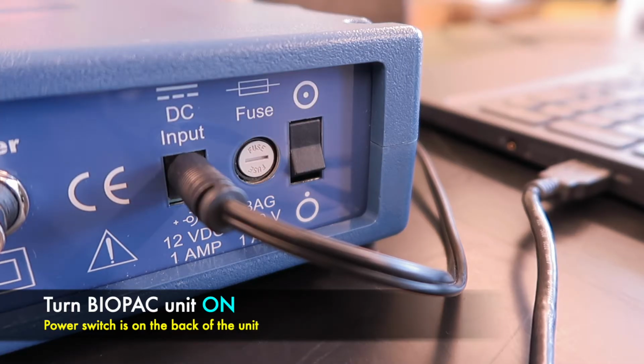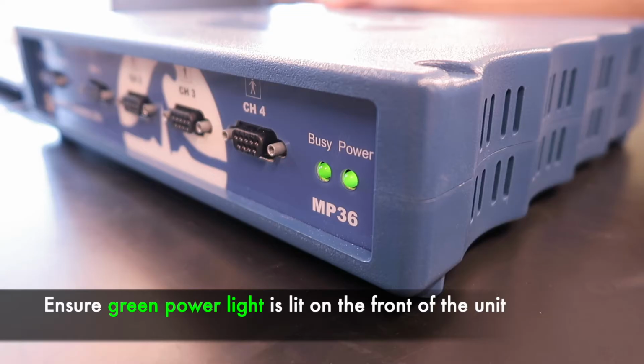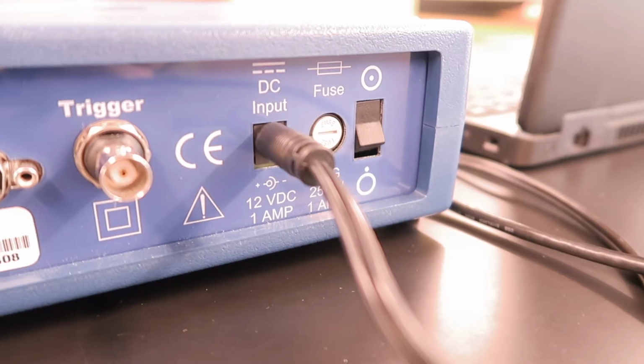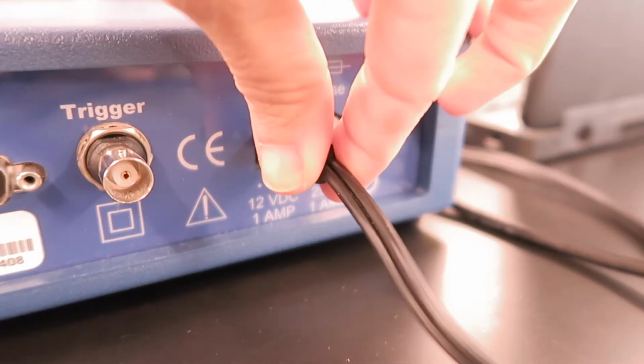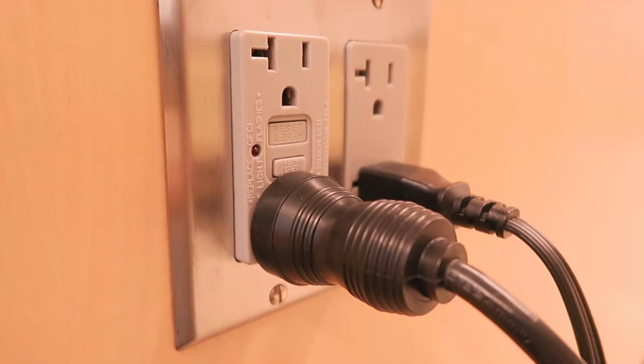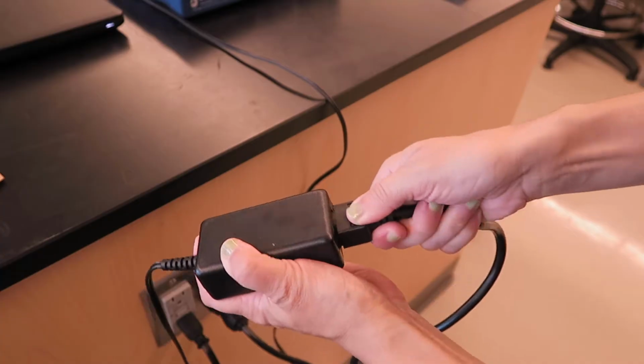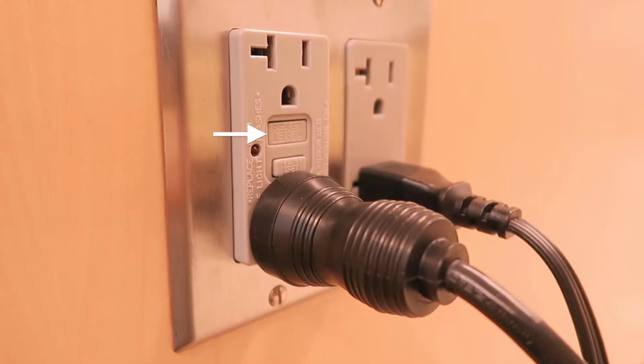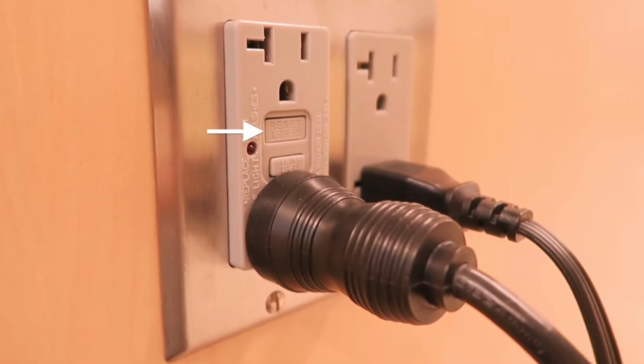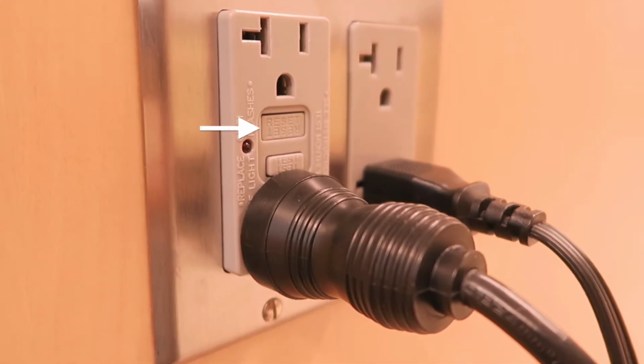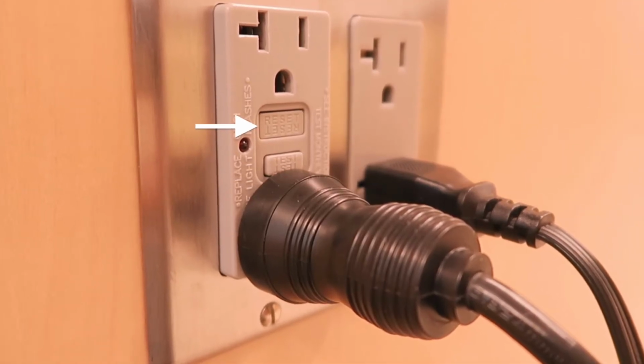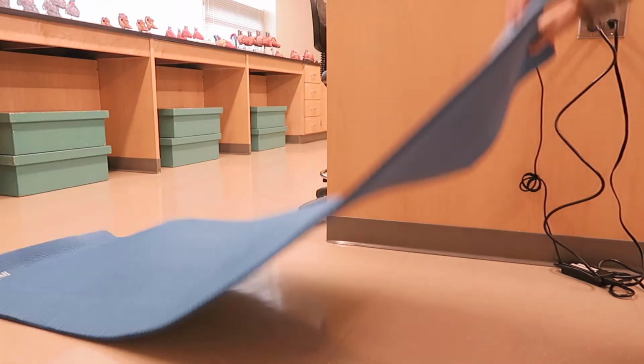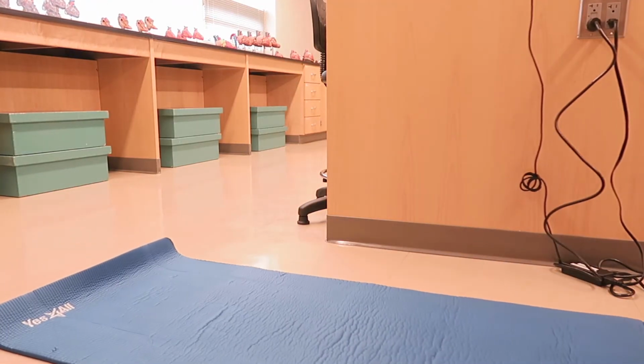With all cables properly plugged in, now turn the power switch on the back of the BIOPAC unit on. The green power light should then light up on the front of the unit under the power label. If the power light does not come on, check the power cable connections at the MP36 unit, the outlet, and adapter. If this doesn't correct the issue, switch ports on the outlet or ensure that the test button hasn't been accidentally pressed. Lastly, roll out a yoga mat near the end of the lab table, keeping it near the BIOPAC unit but giving enough space for your group to stand in front of the recording laptop without stepping on the mat.